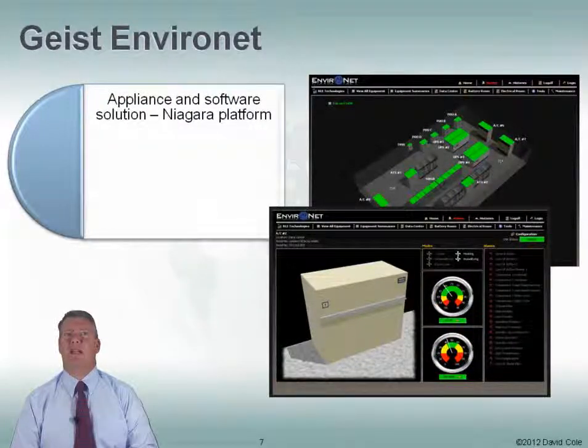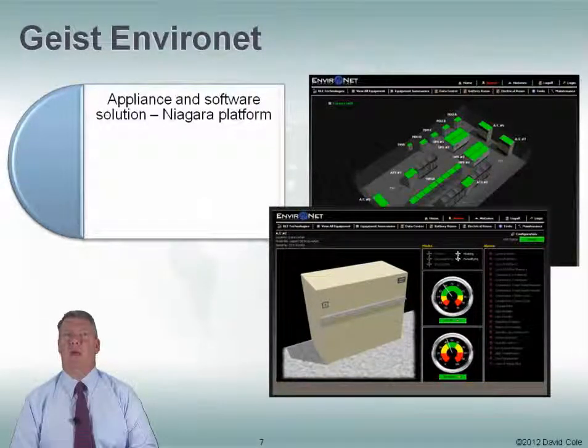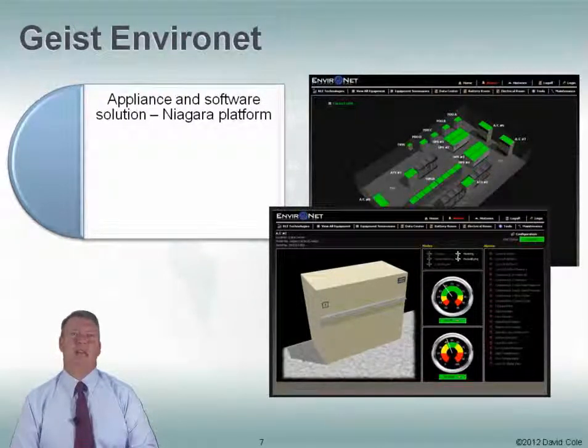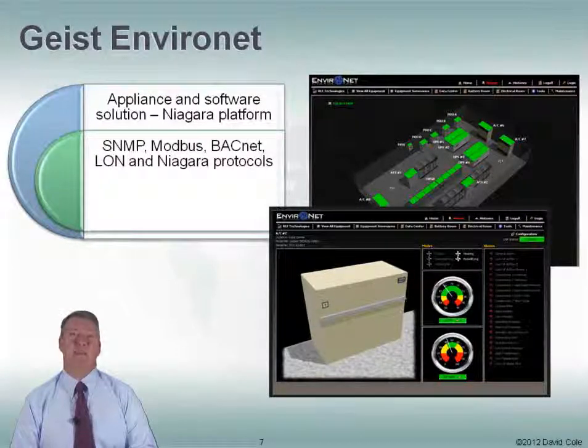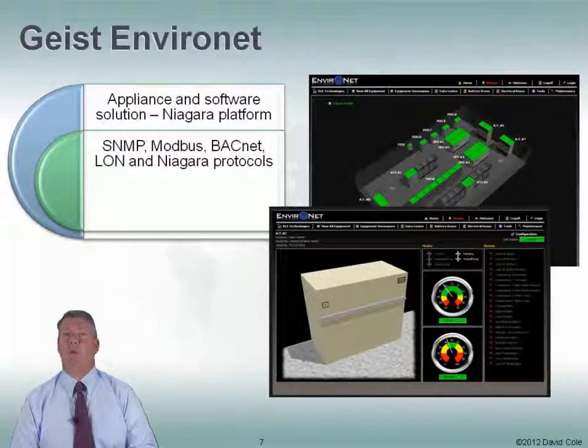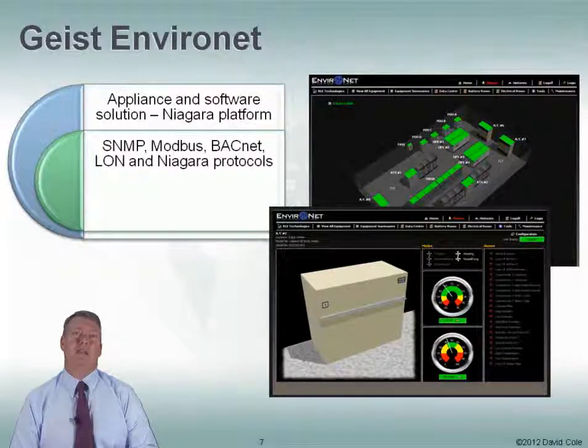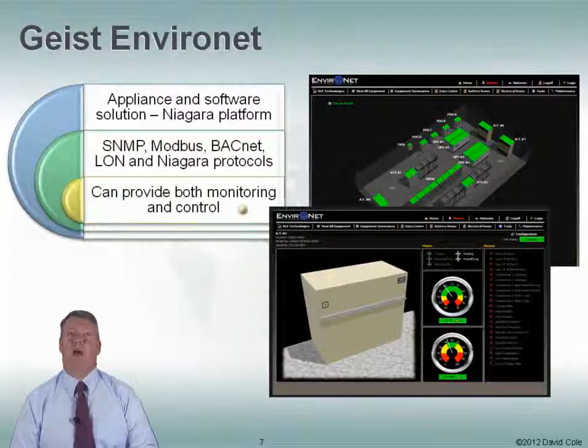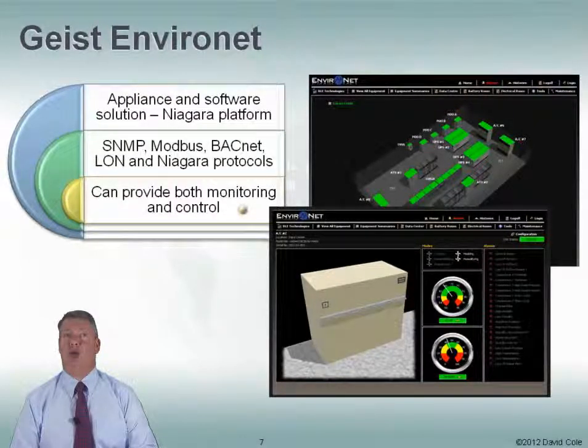Geist Environet — they actually bought this from RLE Technologies about two years ago. It's both an appliance and a software solution. They use the Niagara platform, which provides support for a lot of different protocols: SNMP, Modbus, BACnet, LonWorks, and Niagara protocols. So this software and hardware solution can monitor a lot of different protocols. It can provide both monitoring and control, so you can turn things on and off.